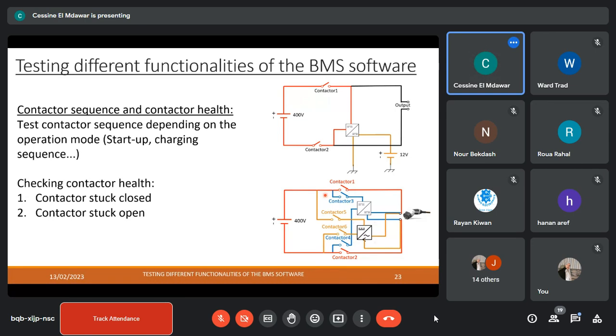The other thing is contactor health. In some scenarios, a contactor might get stuck closed - it gets welded due to the amount of current going through it. If this happens, we need to be able to detect it. Assuming contactor 1 closes and never opens back because of welding from a lot of current, and it's stuck closed - this is a very likely scenario to happen. We need to detect it, and if it is the case, we need to make sure we never close any other contactor. This is also tested in the HIL rig, and it's a functionality the BMS should perform flawlessly, because we don't want a stuck contactor trying to close other circuits - this could cause the battery to blow up.